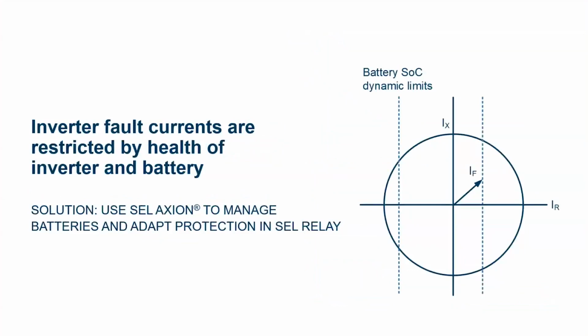Fault currents from batteries, fault currents for low voltage power systems, are not always pure reactive current. They're commonly a good component of power producing current. And where does that power come from on an inverter-based resource? Well, most commonly it's going to come from a battery. And if your batteries are out of service, or some of your batteries are out of service, your fault currents are going to be reduced. We've seen this effect time and again where fault currents depend on the health of your batteries. Real shock to us, but this is a solution we now solve with an SEL Axion acting as a battery management system, giving real-time updates to the SEL relays so we can stay in coordination.